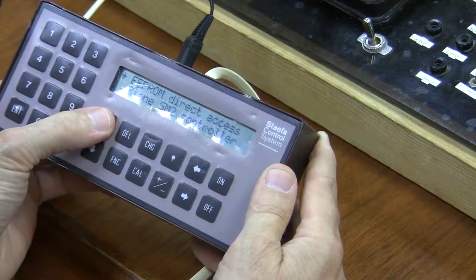So now I'm going to hit enter on set servicing mode, and if you notice, there's actually 3 modes. We are currently in the read-only mode, and that's the temporary mode, and that's the commissioning mode. If I keep scrolling, it's just those 3.